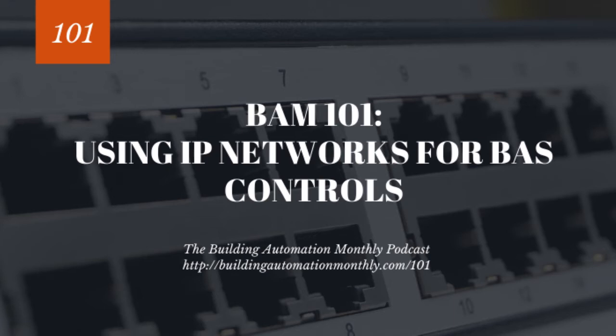We'll find out. So one of the things I've been saying is that supervisory devices' main purpose originally was as protocol gateways, taking field bus networks and converting them to IP or other network level protocols. With IP field controllers coming out, and manufacturers like Easy IO, Johnson, and Distech having field controllers with built-in clocks and some with built-in graphics, is it possible the supervisory device is no longer critical to BAS architectures? Maybe now we can have field controllers, on a small scale, that go directly to a server or host graphics themselves?